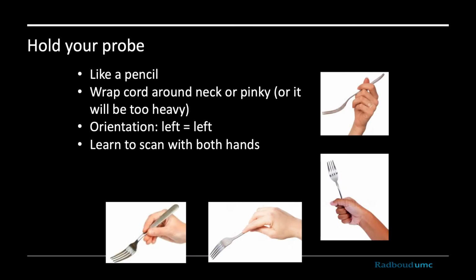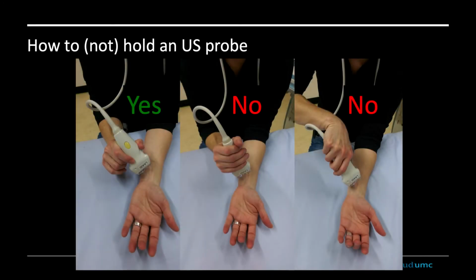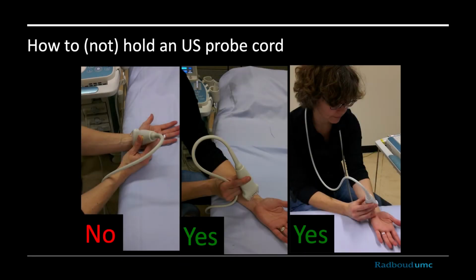Here's a few other probe-related tips and tricks. You should hold your probe like a pencil or a pen, and not like a spade or a fork. And wrap the cord around your neck or your arm or your little finger because it's very heavy and it tilts the scan head away from the ideal 90-degree angle. In addition, it's also a good idea to start scanning with keeping whatever's left on the probe to your left on the screen, because this is most easy to orientate yourself, especially when you're doing interventions with needles. So here's a graphic illustration of how not to hold your ultrasound probe. And the cord, shown here.